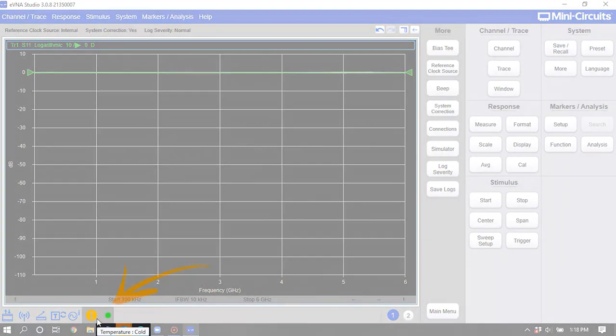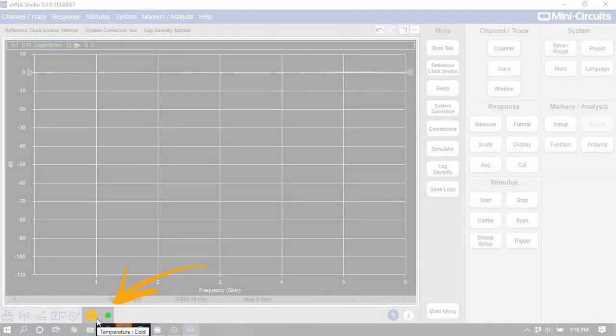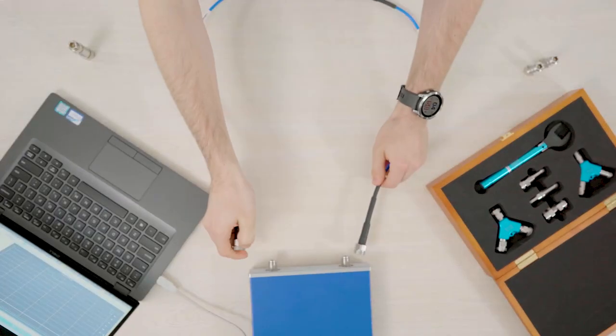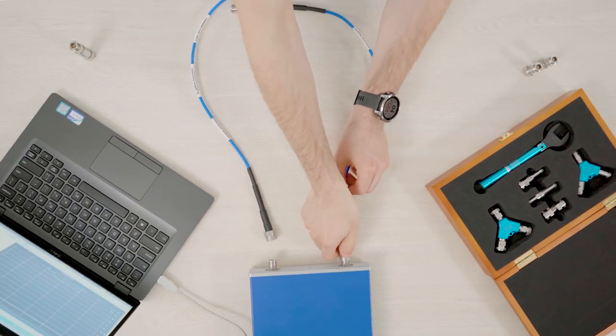Before you start the calibration process, allow the instrument to warm up for about 15 minutes. The temperature indicator in the eVNA Studio software will turn green when it reaches a stable temperature. At this point, connect any required connectors, cables, or adapters between the VNA and the device under test.